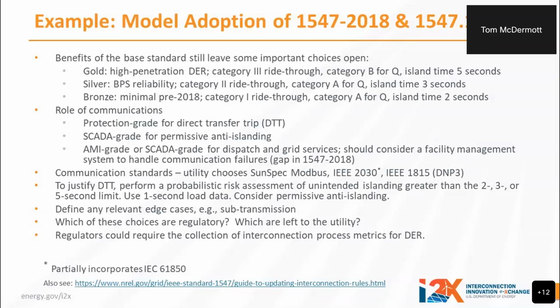So there are disturbance categories, Roman numerals 1, 2, and 3. There are reactive power capabilities, A and B, and islanding time. There's still a preference for 2 seconds, but you can go to 5 seconds, and this is called conditional extended clearing time for islands. It's allowed in the standard. You can also have intentional islanding. And so there are a lot of choices in the standard, and you want to simplify that for entities considering adopting it. And so that's the idea of the gold, silver, bronze level. You can actually make all these choices independently, but maybe there are scenarios where it could be simplified.